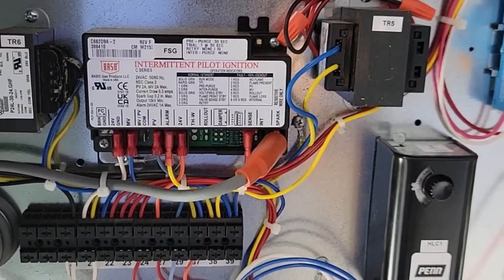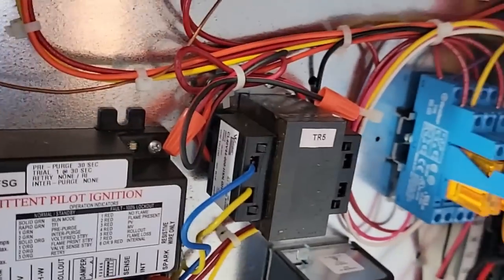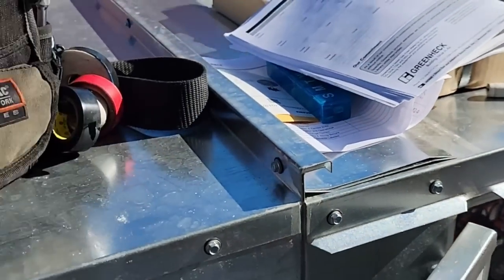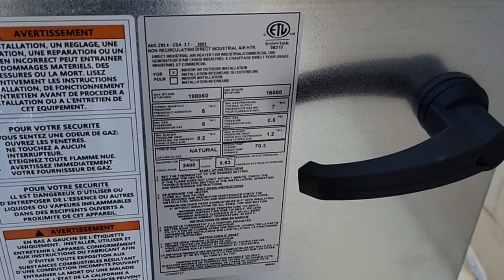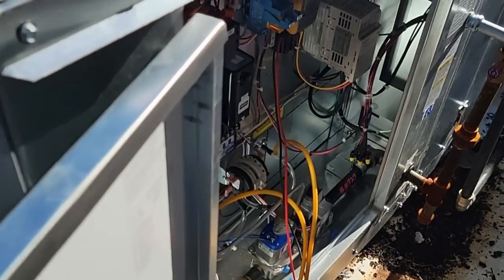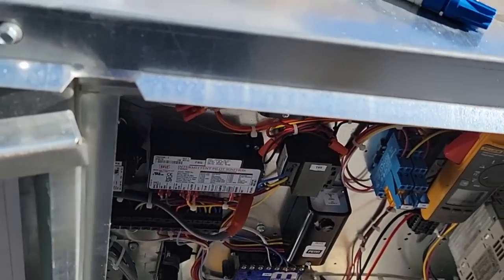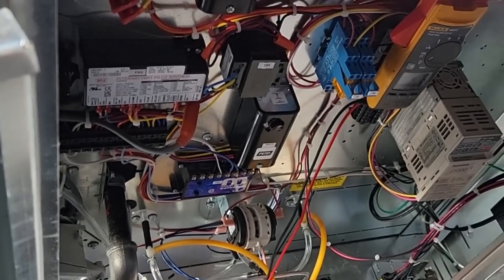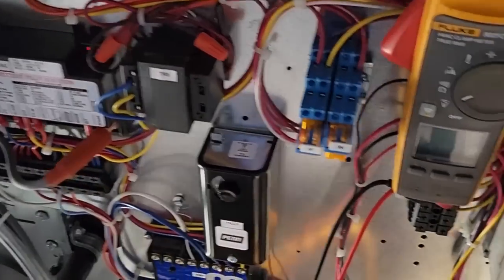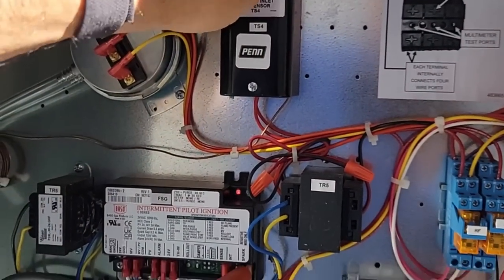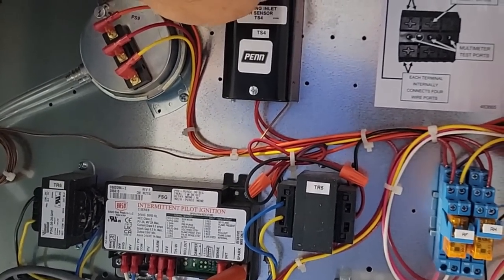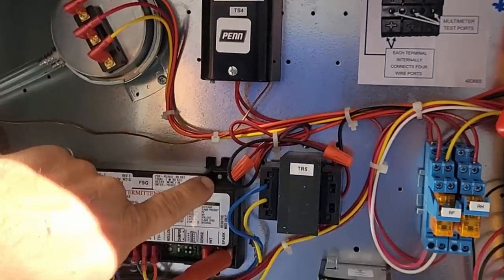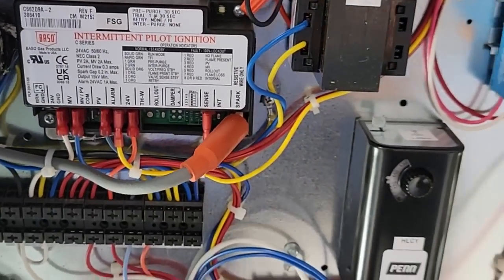This is gonna drop out fairly quickly because of the BTU this thing is rated at. Any of them actually do, but this is a 200,000 BTU potentially with a minimum of about 16,000. They don't really wanna dump that kind of fuel in there and have it not ignite. So we're gonna do this again. And we should be able to turn the stat down. That should break it. Yep. Bring it back up. Hit reset. We'll let it try again.